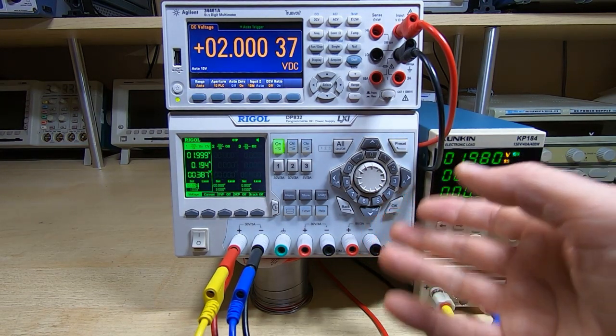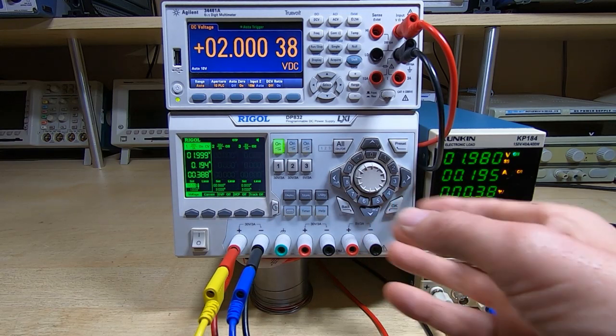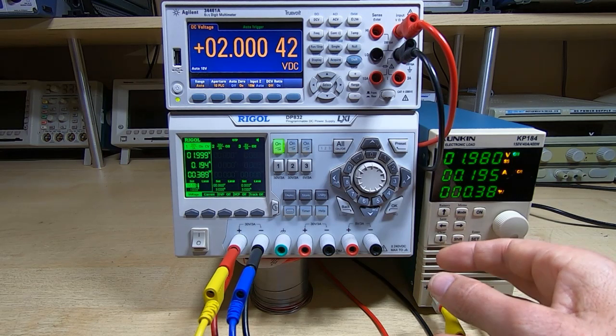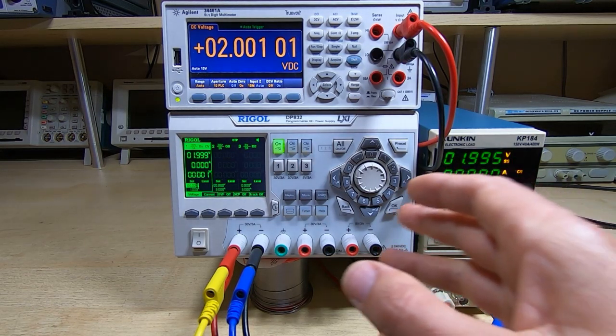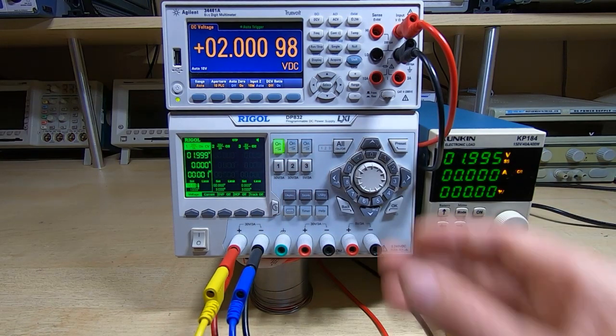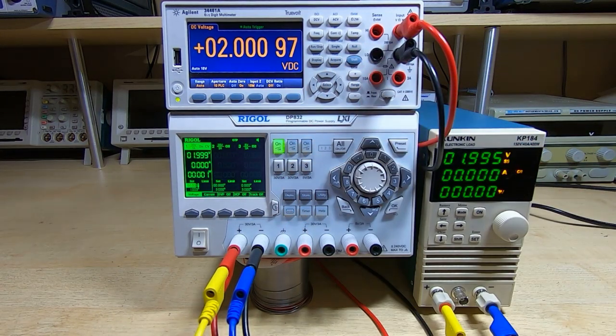It didn't before too much; it was just that it was off by several millivolts. So it's looking like the fix, getting rid of this noise, has also improved effectively the accuracy and really the resolution of the power supply as well. It's well worth performing this fix, and it might even be indicative of whether you need to apply this even if your supply is not resetting. If you're getting these little jumps in the millivolt range, then it could be that your machine needs to have this fix applied to it.